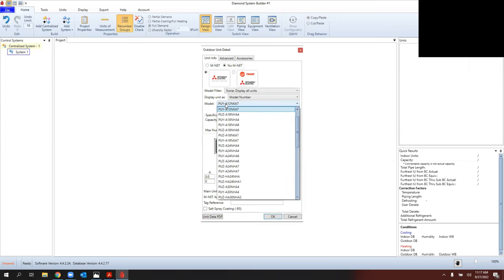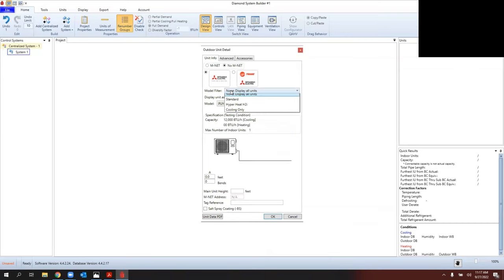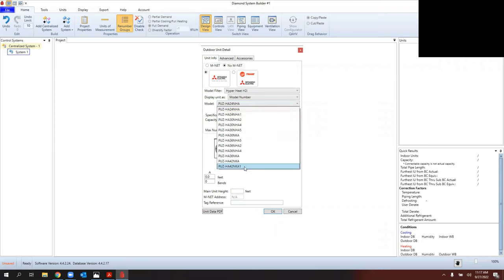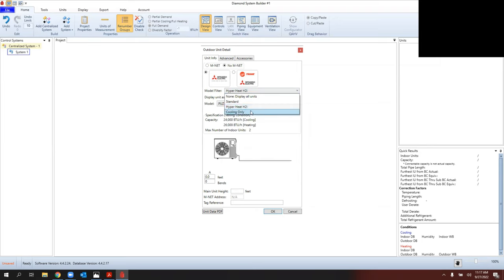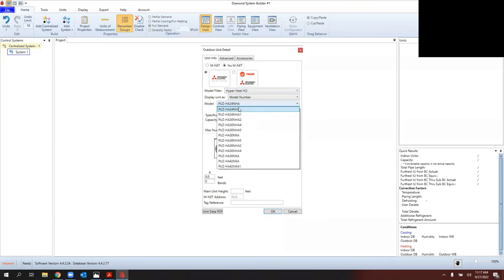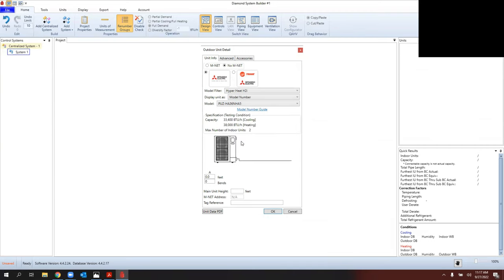I'm going to select a P Series for a one-to-one ducted system. When I select OK, it pops up all P Series condensers in capacity and generation order. There are model filters — I can select just Hyper Heat models, which narrows it down to two through three-and-a-half tons. I can also select cooling only or standard variable speed heat pumps. I'm going to keep a Hyper Heat ducted system — a three-ton one-to-one Hyper Heat. The revision numbers are shown; the most recent is the dash-five.